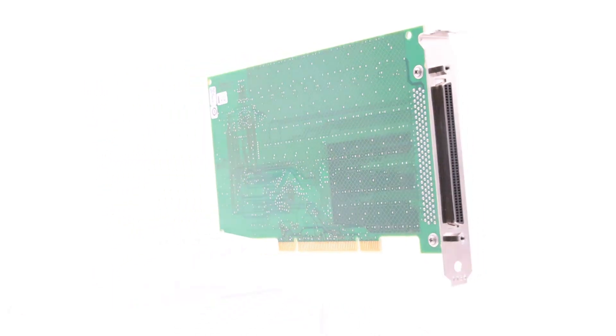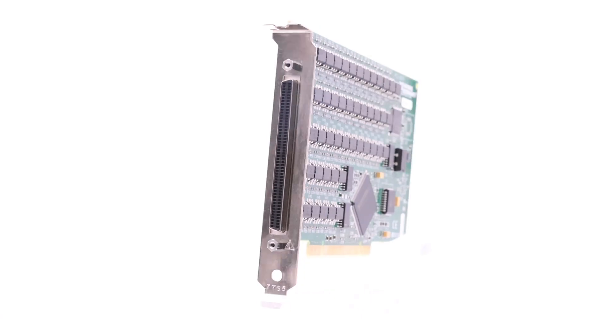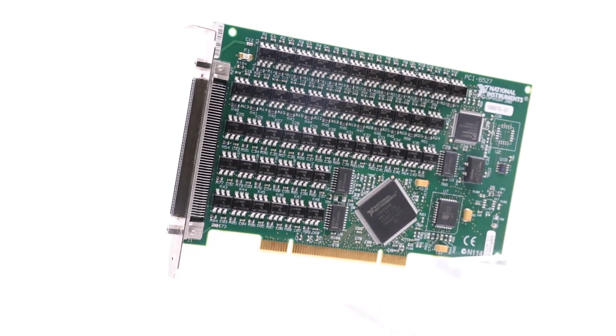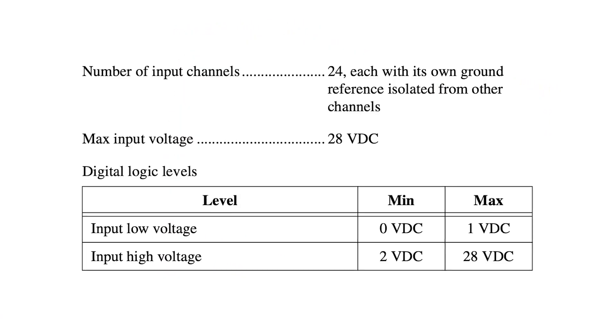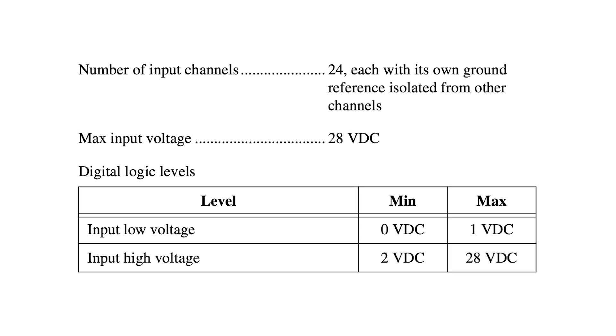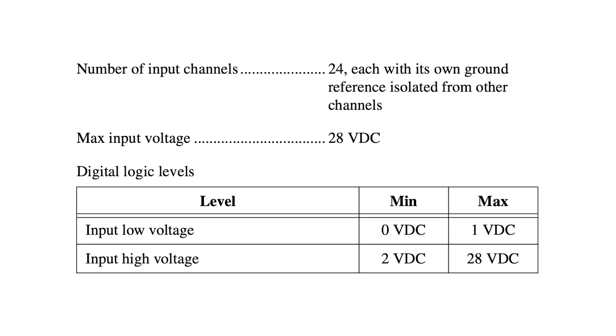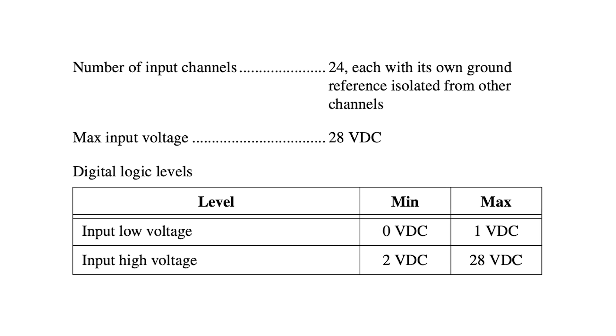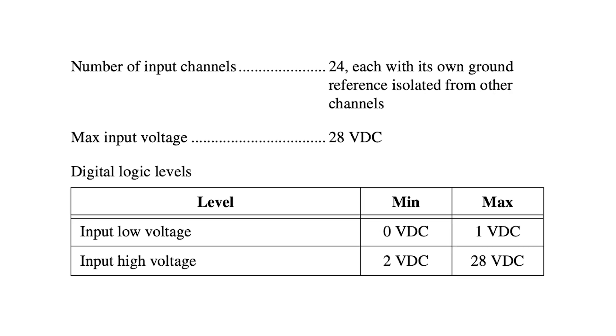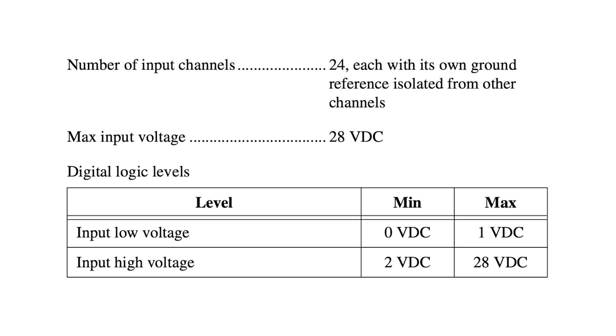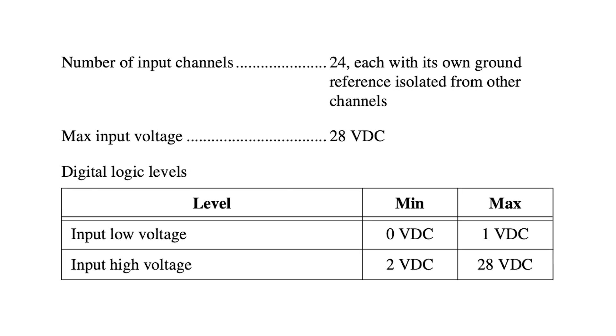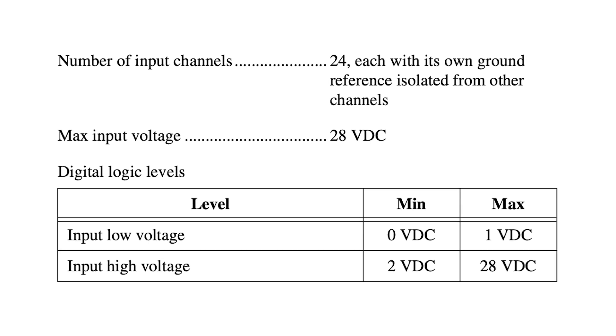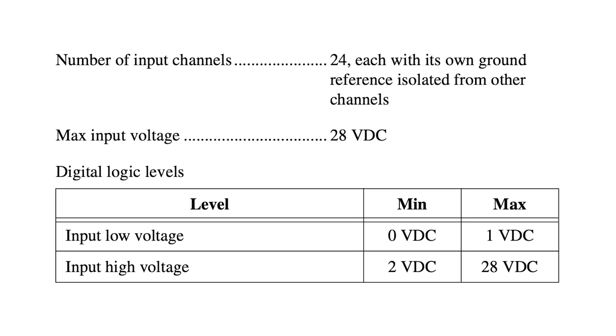This 48-bit device boasts 48 channels capable of acquiring isolated digital data, with 24 solid-state relay output channels and 24 opto-coupled input channels. Each input channel features two differential isolated terminals for signal and reference, supporting logic high with a voltage difference of 2 to 28 VDC and logic low between 0 and 1 volt.